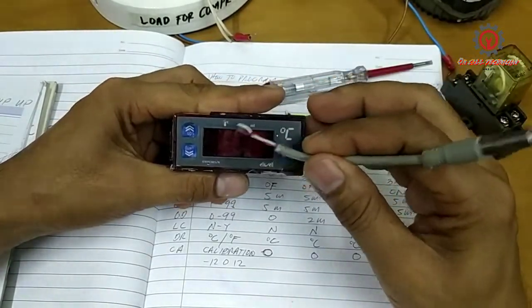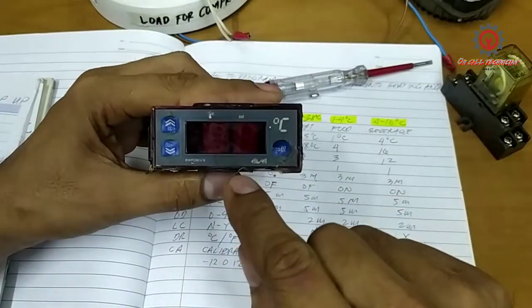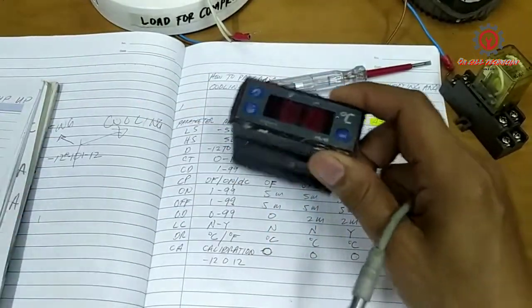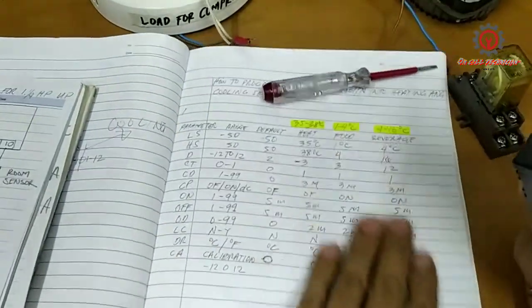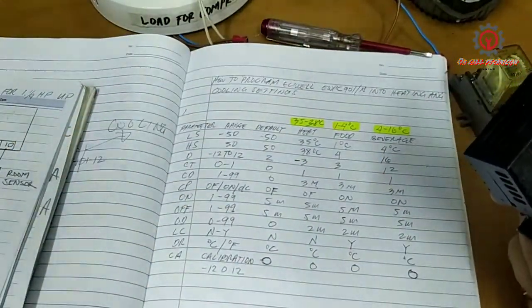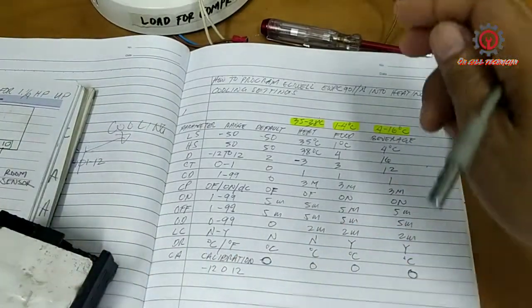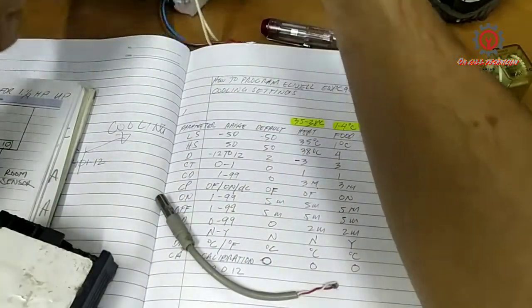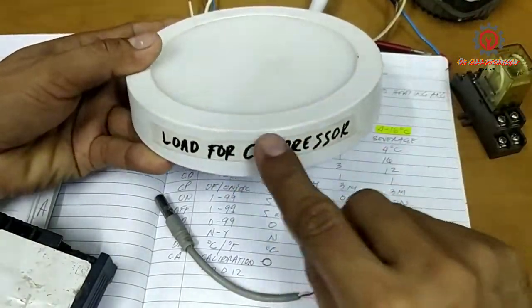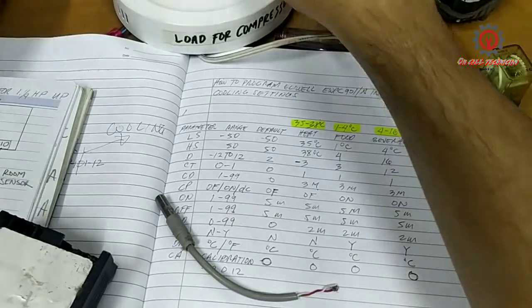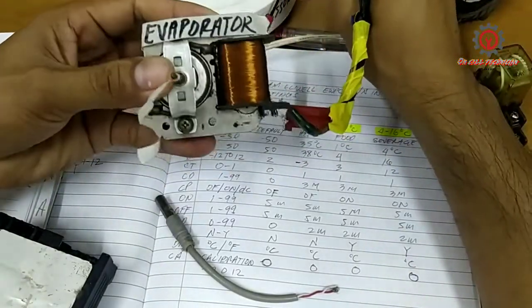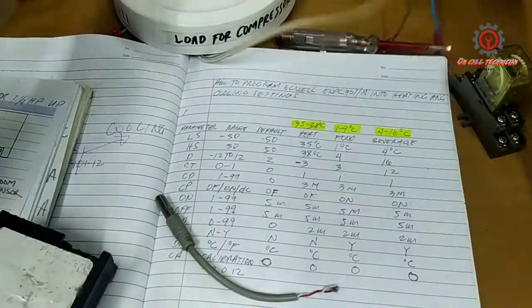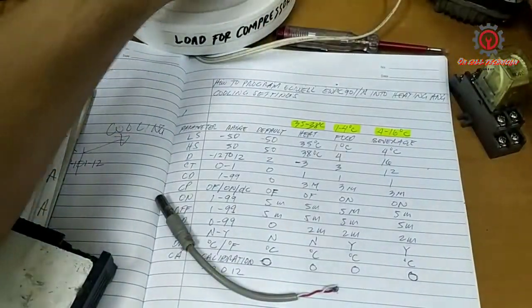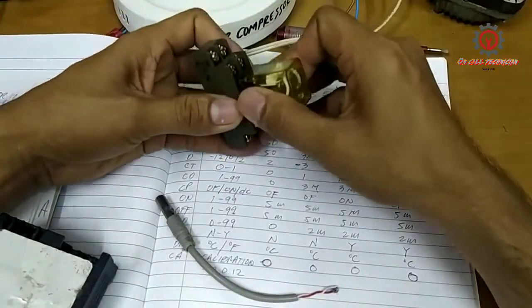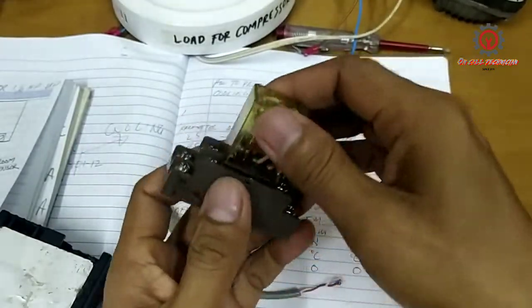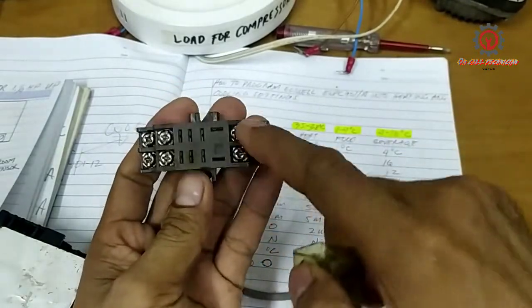Today we're going to wire this Eliwell and we're going to program it with safety for the compressor, and this is our load for the compressor. This will be our evaporator fan motor and a condenser fan motor, and we're gonna use a double pole, double throw relay here, and this side here is the coil.